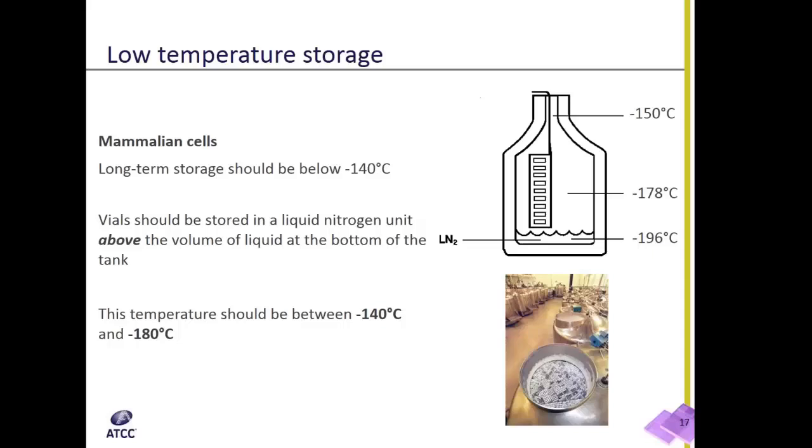Since metabolic activity is arrested at minus 140 degrees, the additional cold temperatures of the liquid phase offer no real advantage. However, immersing material in the liquid phase runs the risk that some of the liquid nitrogen could penetrate and damage the plastic vials.